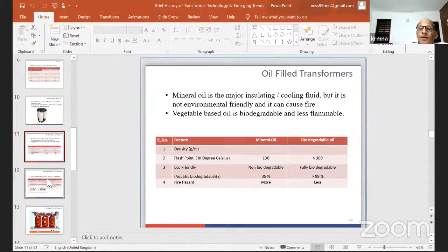Then the next development was silicone fluid. Silicone fluid is basically synthetic, and it has the advantage that it can withstand very high temperature, and it is less flammable. I would not say that it is highly flammable. It is less flammable only. That is, when temperature goes to say 300 degrees or more, it can catch fire. But it will not catch fire at a lower temperature like mineral oil. Mineral oil will catch fire very quickly; at about 140, 150 degrees mineral oil can catch fire. Whereas silicone liquid or similar type of silicone liquid is one category.